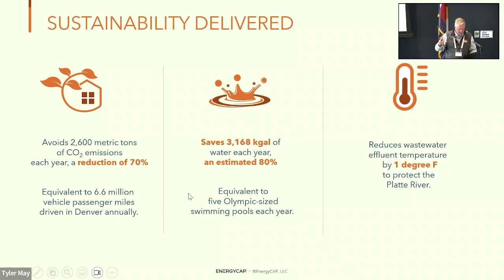We got two pieces of good news back. One, the heat exchanger process is more efficient than the conservative engineers said it would be, so we're getting better efficiency in the heat exchange process. The second thing is the ambient loop is more efficient. HDPE buried in the ground does not have very much thermal loss, so it can run in this null mode a lot because we're not losing as much energy in the ground as we thought.